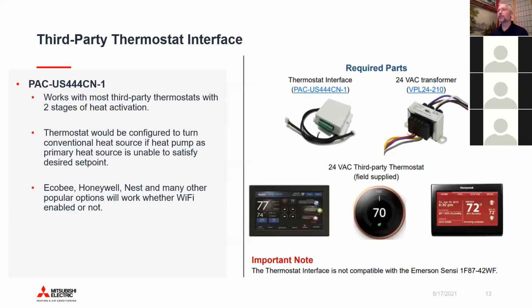Okay, so then the next option, right? Third-party thermostat interface, delightfully labeled PAC-US444CN-1. This allows you to integrate any thermostat, pretty much everything from the old-fashioned Honeywell round all the way to Nest and beyond. If you don't have 24-volt AC in the house already, you will need a 24-volt AC transformer. Typically, you're going to have that on site if there's already a conventional heating system. And you can see that the clamshell here opens up, and that's where the dip switches are.